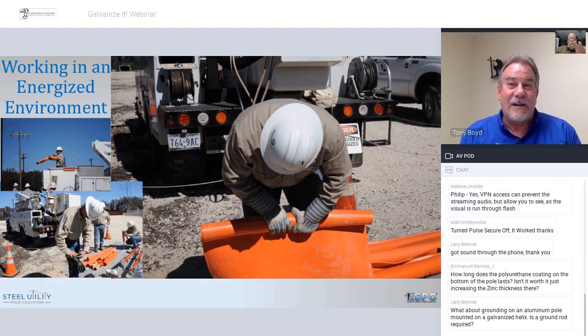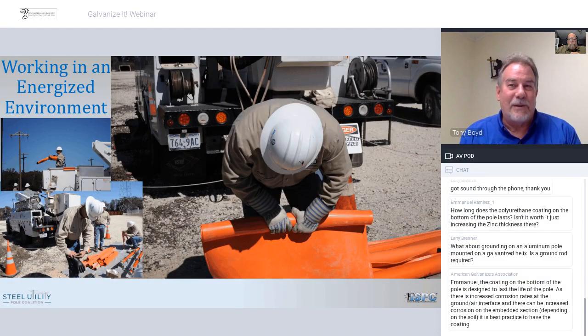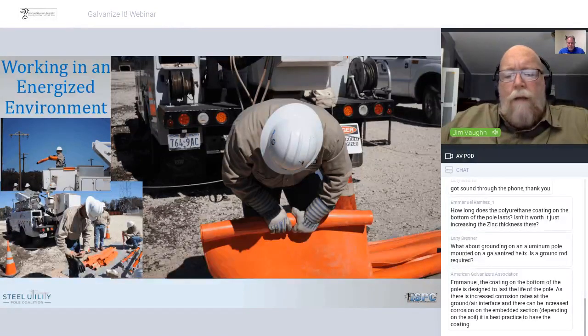On that last slide, one of the things that we were talking about is the system neutral. They put an insulator, tie the system neutral, and then bond it to the pole. So I don't know why they would use an extra insulator on that system neutral and then bond it right to the pole. But anyway, Tony, there are a couple of technical questions, and one of them got answered for a manual about the polyurethane coating. As far as I know, and I see a technical answer there, it says that that polyurethane coating will last forever, as long as the life of the pole is.